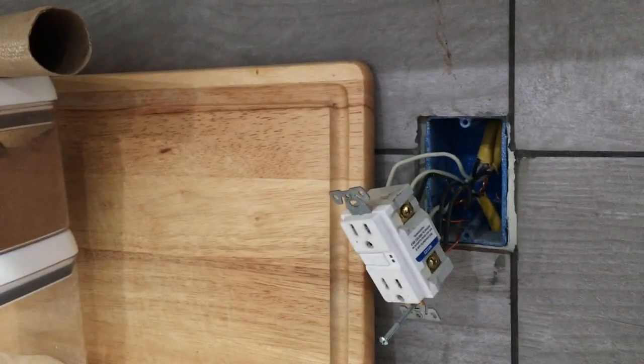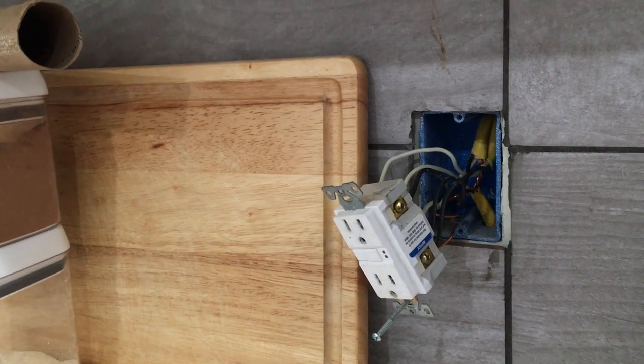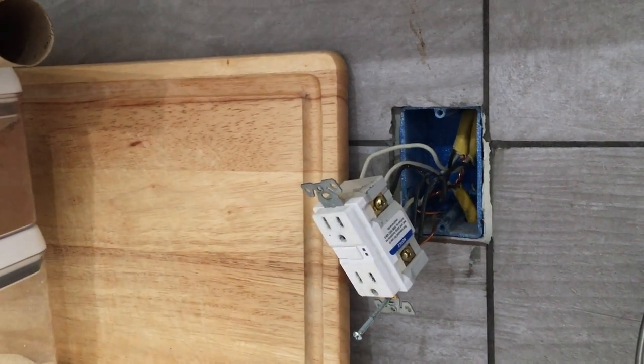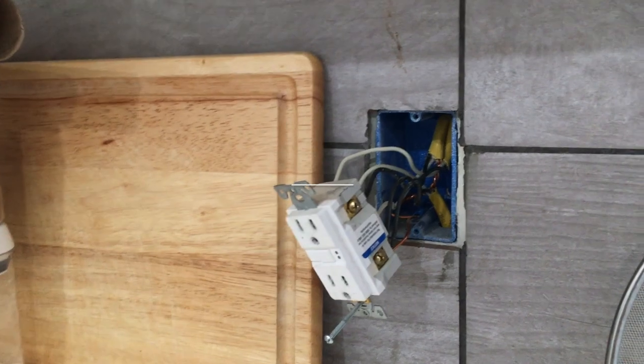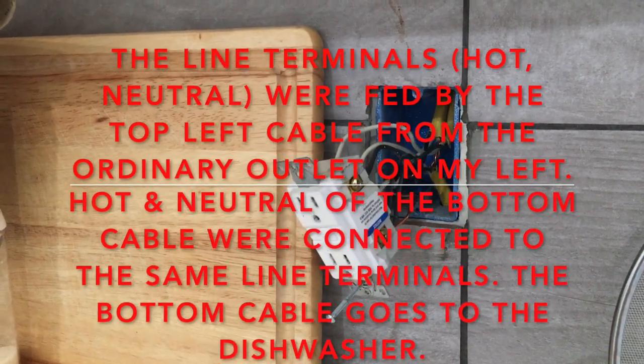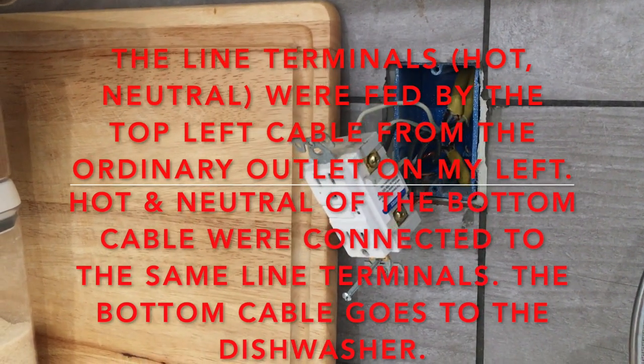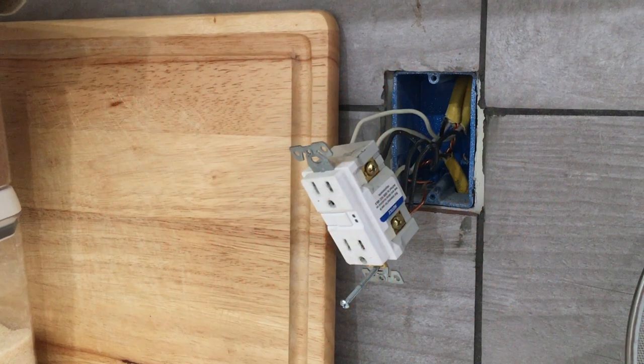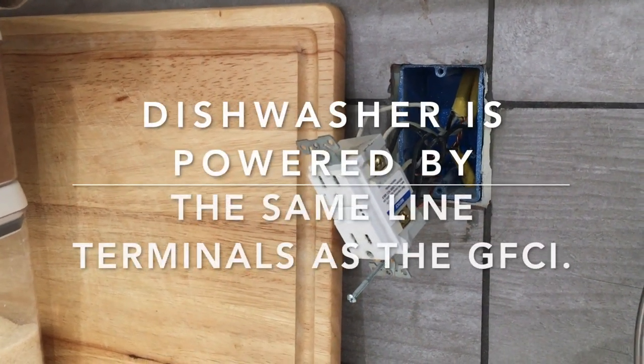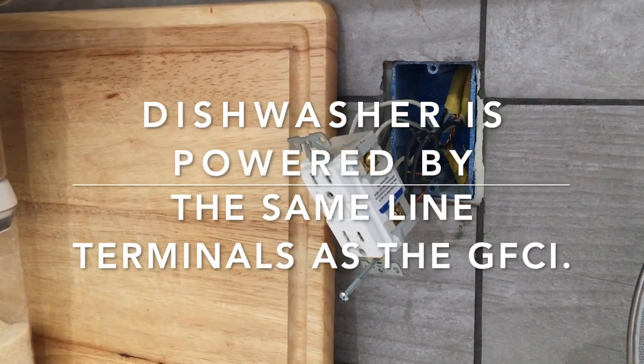The top left cable that feeds this GFCI goes into the line terminals on the back of the GFCI, and also attached to another position on those same line terminals is the bottom yellow cable, which goes to the dishwasher underneath this outlet.